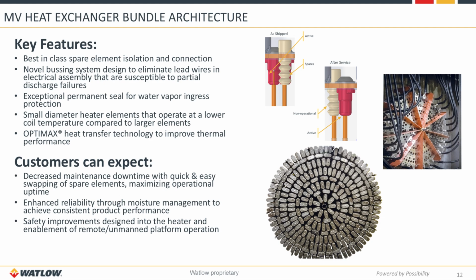The last slide I'll talk about is the medium voltage heat exchanger bundle architecture. Our system offers the best-in-class spare element isolation and connections, as shown in the top two pictures that demonstrate how a spare element will look as shipped, and then how that spare element becomes an active element if it requires any service. We also have a novel busing system design that eliminates lead wires entirely.